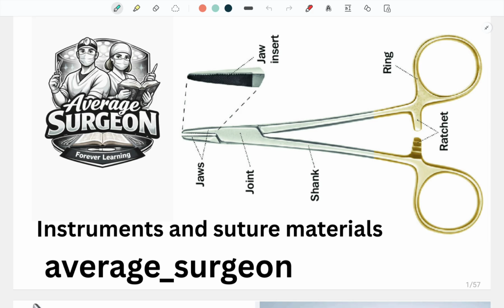Except sharp objects, you should not autoclave sharp objects such as scissors or any kind of needle, because if you put them in the autoclave, crust formation will happen and there is a loss of sharpness of the instrument. So always avoid putting sharp instruments in the autoclave. For sharp instruments, there is an ethylene oxide chamber available, or you can put them in 2% glutaraldehyde, or in Cidex, or in diluted Lysol solution. So never put sharp instruments in the autoclave.